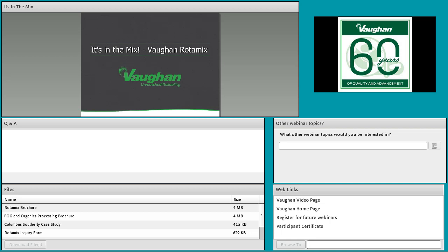Okay, so most of the time, an engineering spec will define the sludge content at say 4 to 6%, and we never want to short you on mixing capability, so we will be sizing everything for that 6%. But if you really only have 4% most of the time, we might run at 90% speed or 80% speed, whatever optimizes your gas production in the digester for the minimum amount of electricity used. Also, we have a reduced energy strategy where we run at full speed for a couple hours a day and a reduced speed the remainder of the day. Hopefully that answers your question.